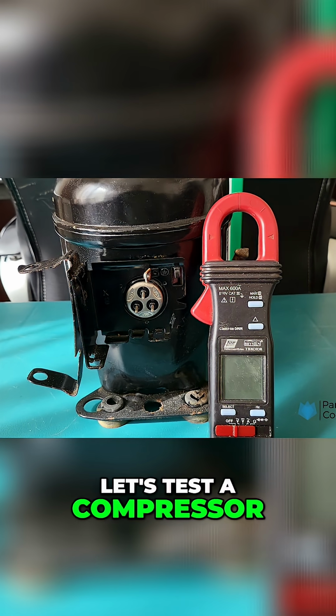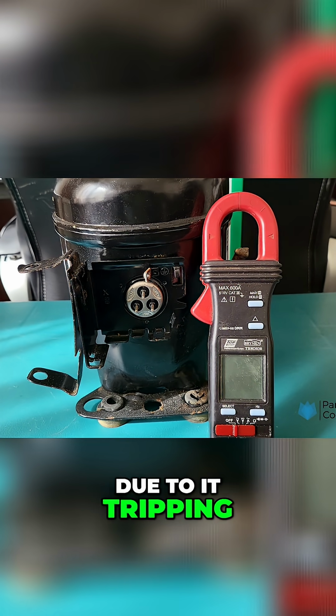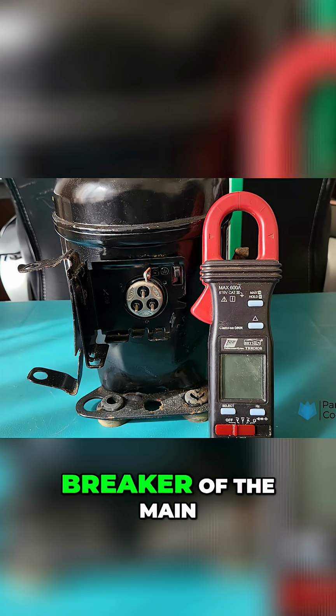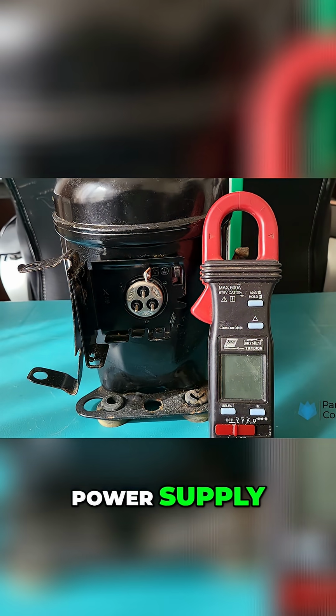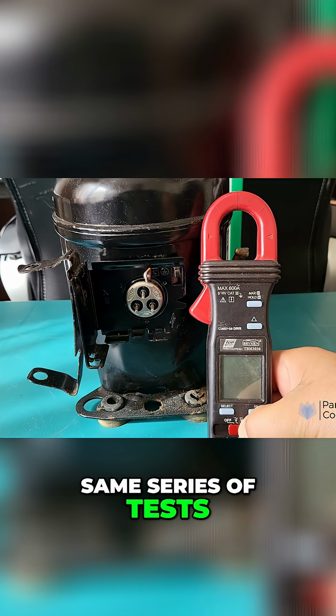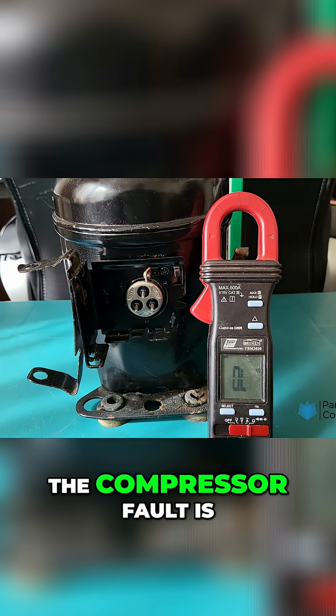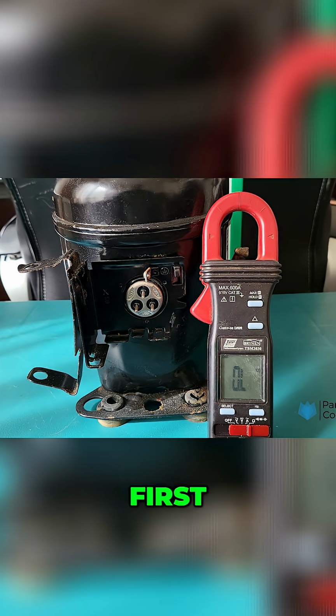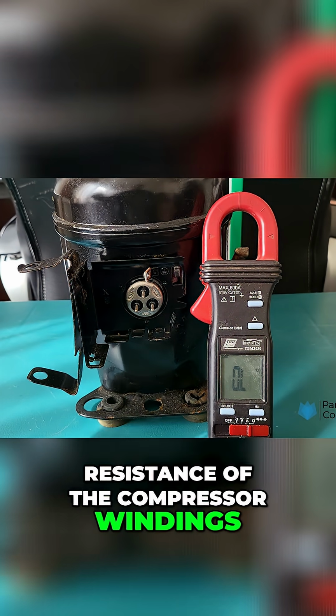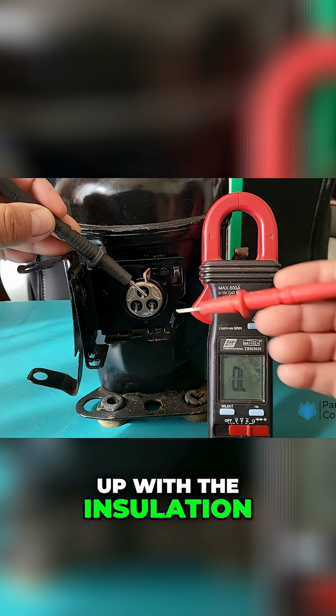Now let's test a compressor that has been condemned due to it tripping the earth leakage circuit breaker of the main power supply. We will use the same series of tests to determine exactly what the compressor fault is. First, we will test the resistance of the compressor windings, and then follow that up with the insulation ground test.